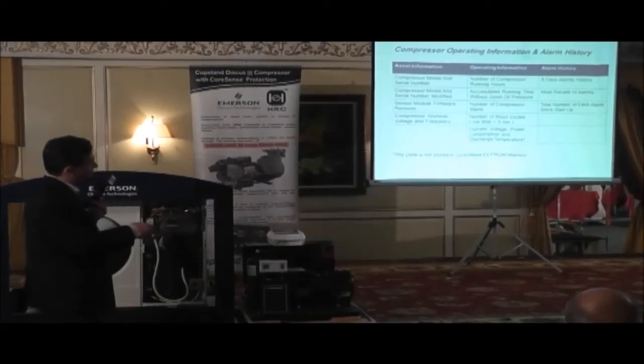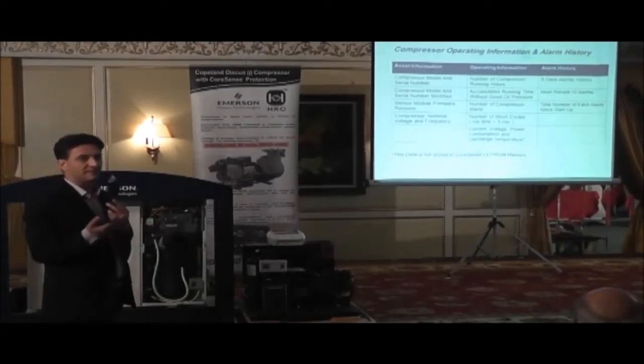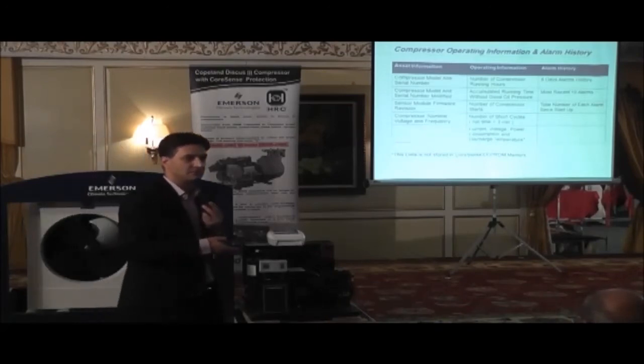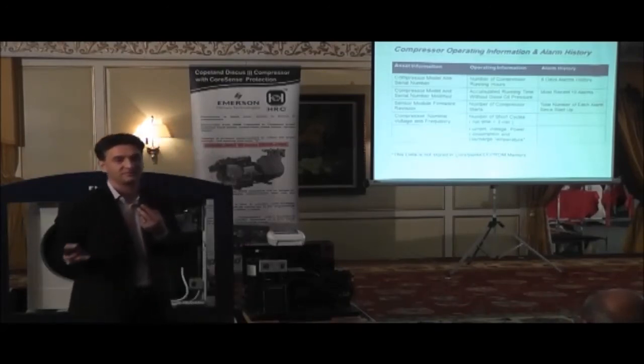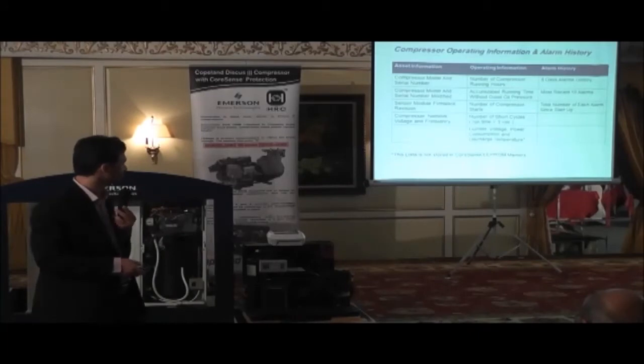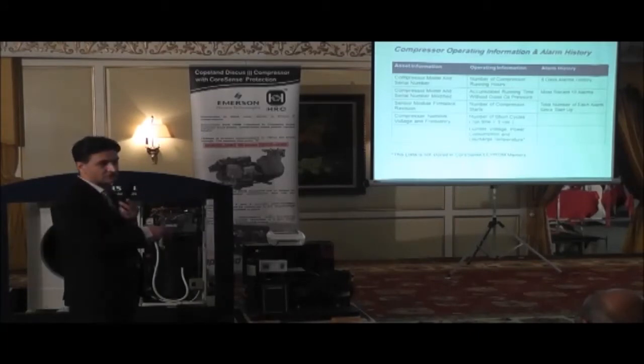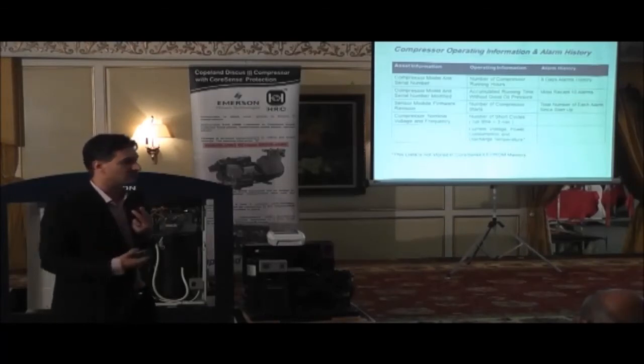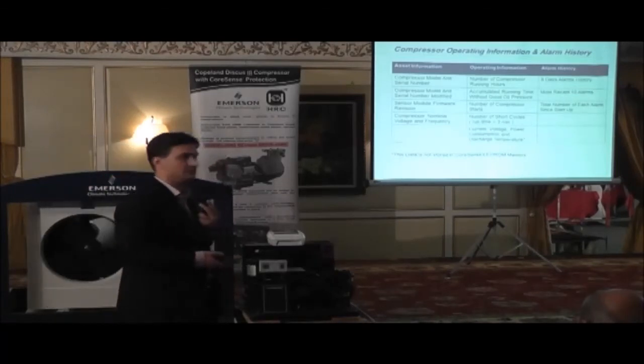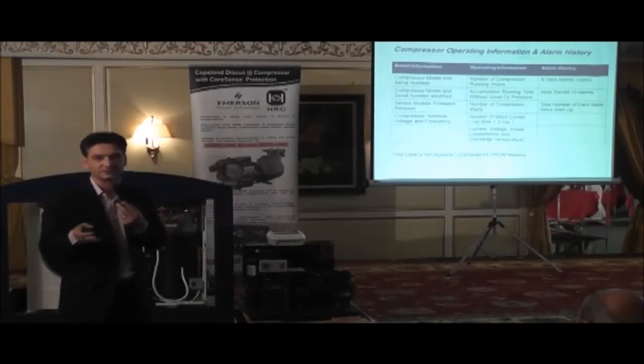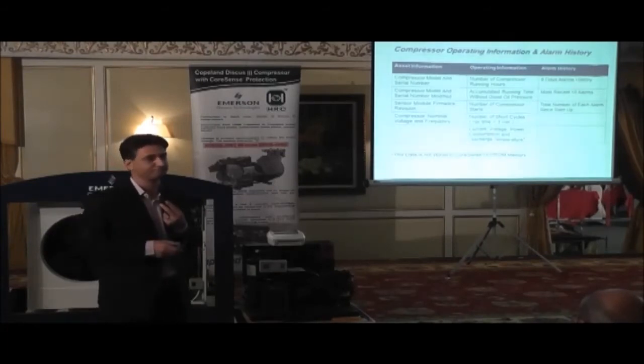It will then give you a readout on oil pressure. How many times has it tripped? How many times or how long has it been running with good oil pressure? Number of compressor starts. So this will help you diagnose if you have short cycling problems in the system. Because typically we want to restrict the number of starts to 10, 12 an hour.